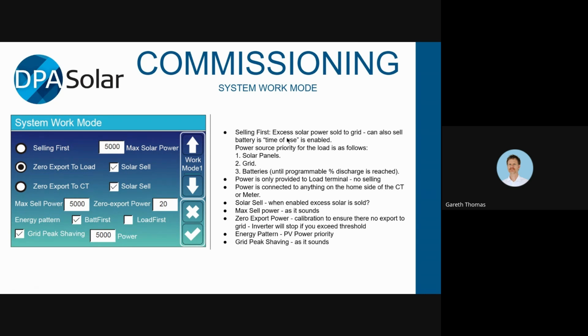So selling first, if you're in this mode, then excess solar power will be sold to the grid. If you have a function called time of use, which I'm going to explain in a moment, and it is enabled, you can also export battery power as well. You would use that, for instance, if you wanted to export battery power at night. So you charge your batteries up during the day, and then in the evening, you might discharge your batteries at night just to make some money. Or if you didn't have a meter in the main switchboard for some strange reason, you might set a small amount of export to cover what your loads are during the evening.